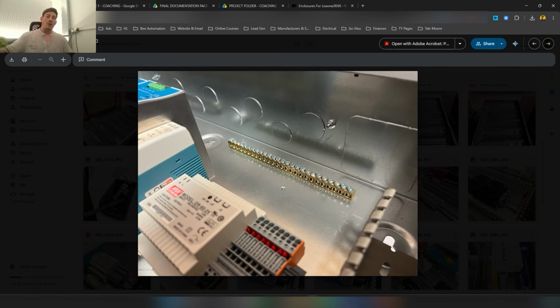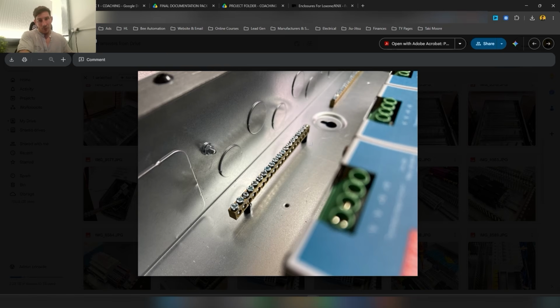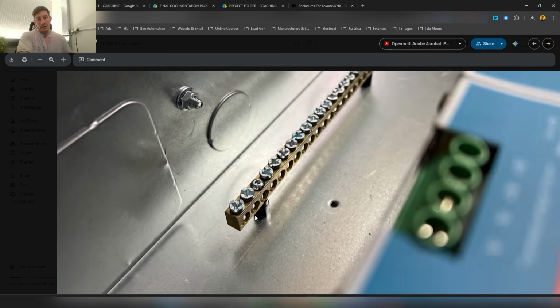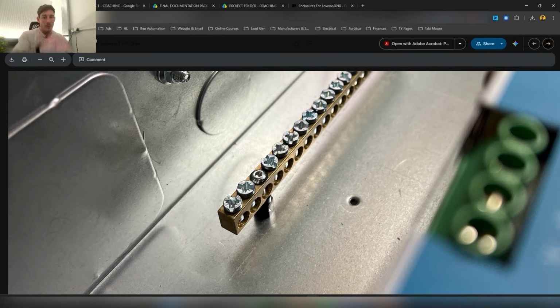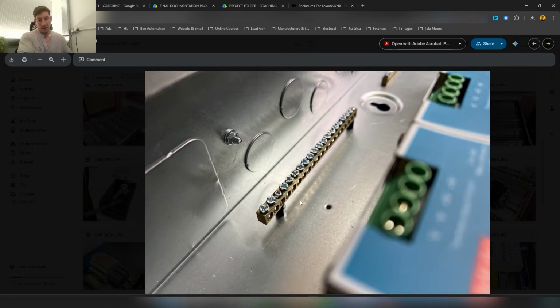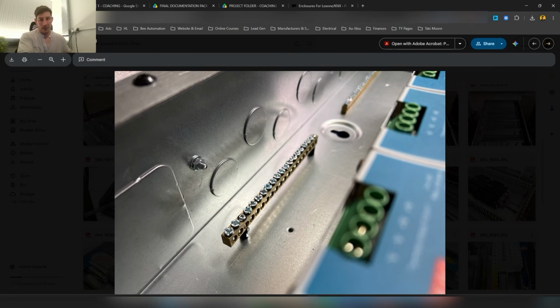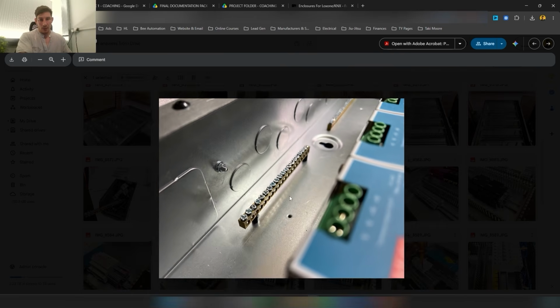As you can see, what I was talking about earlier, this is the earth block we're using, mounted to the metal enclosure, because we want the enclosure to be earthed, and that was moved from the bottom up to the top. Same thing with the neutral bar, the only difference is these are raised up off the back of the enclosure using nylon spacers, because we don't want the earth and the neutral shorting out together.